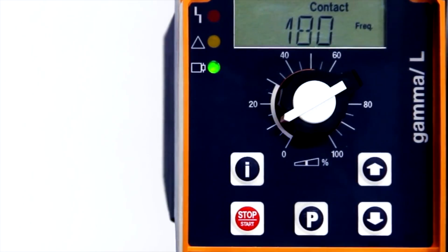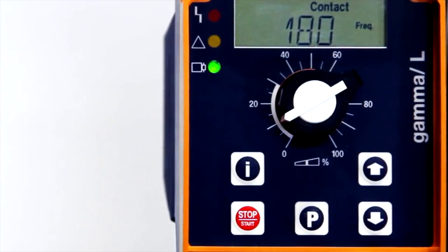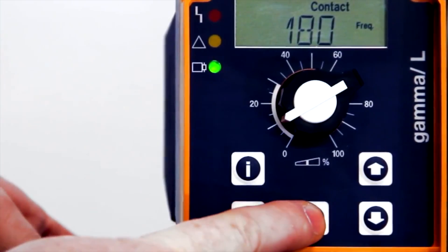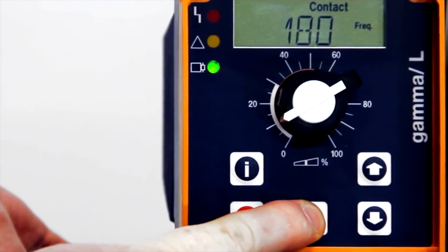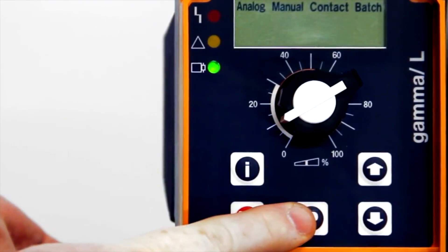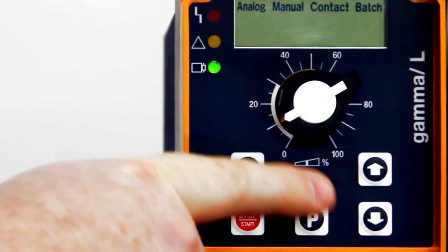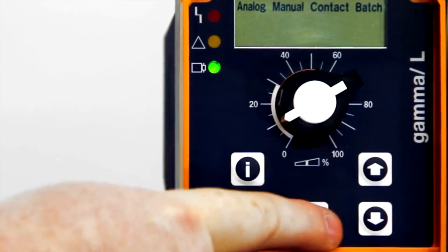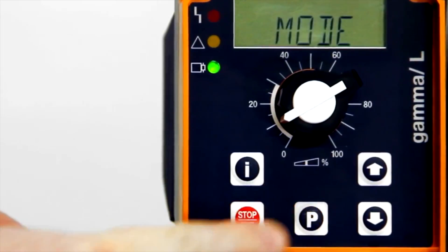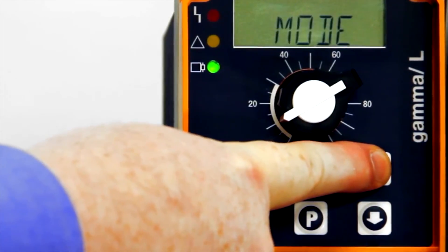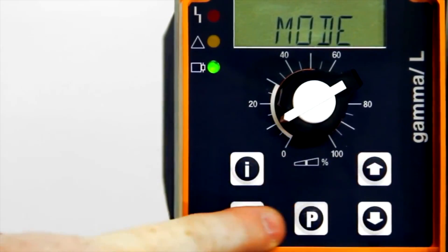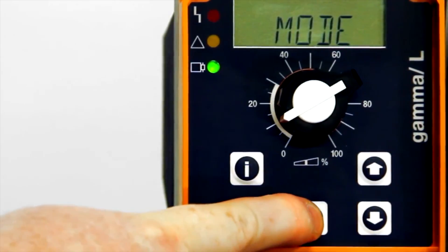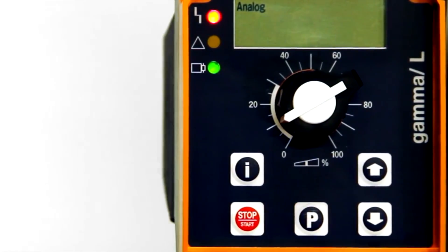The next mode of operation we'll talk about is the analog mode of operation. Typically, that's a 4 to 20 milliamp signal. Again, we press and hold the P key until we see the word mode flashing. We use the up or down arrow buttons if something else comes up. Press P at mode. Now we scroll again with the up or down arrow key until we see the word analog flashing. We press the P key once quickly, and we're in the analog mode of operation.